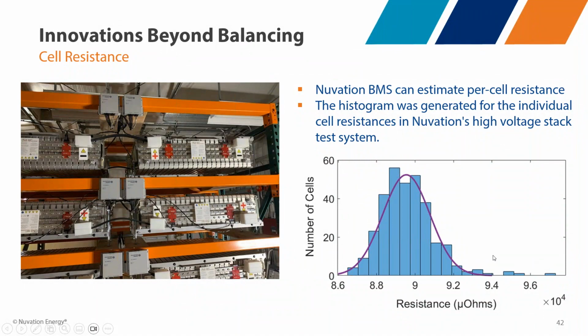Getting this kind of data out of a battery management system can give an early indication of cells that may require servicing or replacement. Ahead of this becoming an issue that really limits the system, this can give you a soft warning that the next time you're out servicing the site, you may consider replacing some of these cells. This same resistance data is what's used inside of our continuous balancing algorithm, in the model of the cell, in order to calculate the cell's open circuit voltage.